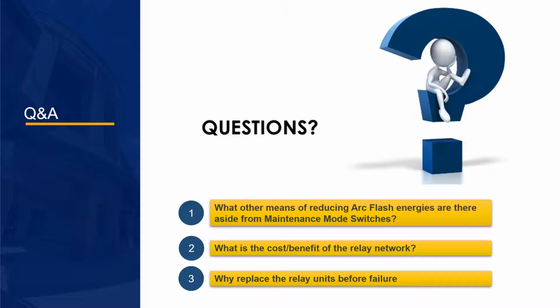Question 1. What other means of reducing arc flash energies are there aside from the maintenance mode switches? Arc-resistant switch gears are an option. They are designed in a way to direct arc flash away from the front of the gear where operations take place. As this project was a retrofit project modifying existing switch gears, this wasn't an option.